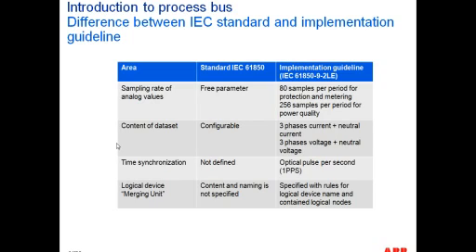Then another issue that came up was in terms of the configuration of the data set contained inside a sampled values data stream. And the definition that the implementation guidelines make is that each sampled values Ethernet frame will contain a data set which is composed of 3 currents for A, B, and C, plus a neutral current, which is 3I0, and then 3 phase voltages, meaning phase A, phase B, and phase C, plus 3V0, your neutral voltage. So what that in turn allows manufacturers to do is to design merging units and IEDs that can consume this type of information.